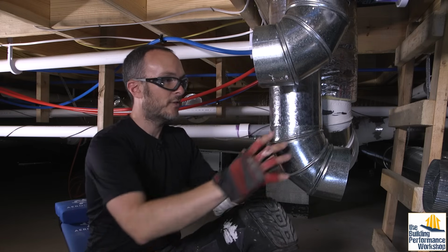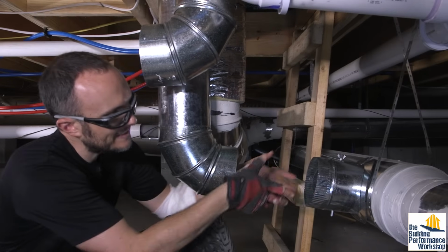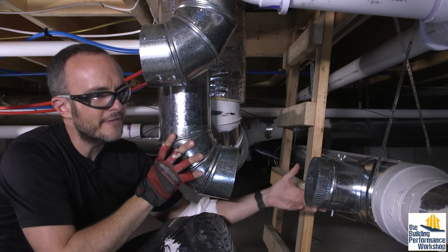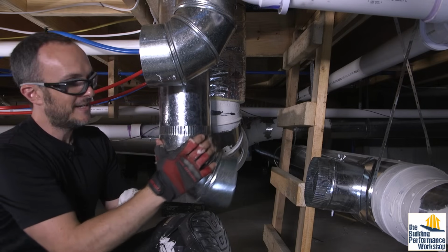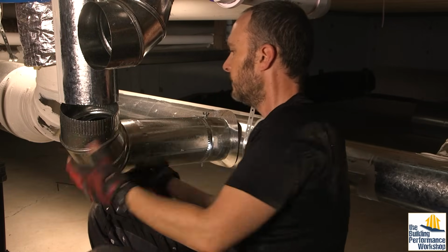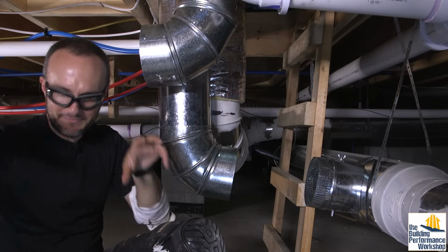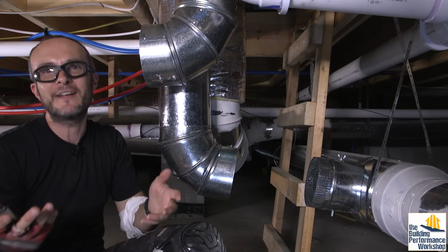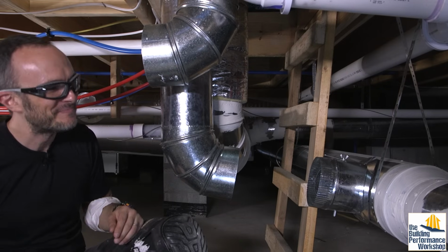Because not only do I need the room for this 6-inch duct, I also need the room to be able to work around it and connect this piece here to it, which means I need to be able to move this, rock this back and forth before I had installed it. And of course, the way that I'm doing this now is you got to think ahead about these things. You connect this to that, and then I'm going to slide this up into it. But I've been caught plenty of times now on this install where I'm connecting things, and then the one piece that's in the middle, I can't move either side, so now I have to figure out, how am I going to do this? Flex duct is one of the ways that you can figure that out, by the way.